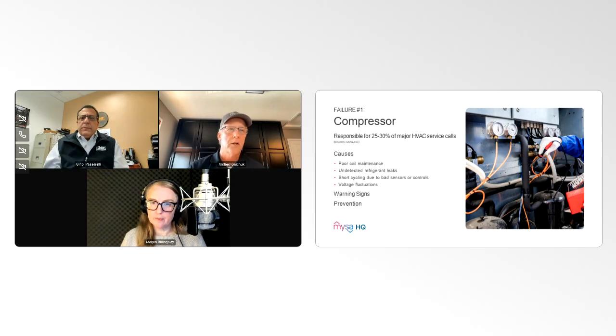The compressor itself may be running intermittently. So when we look at this runtime report here, if you look at, for example, the indoor line, where I can see the temperature decreasing and increasing and decreasing over the course of a day, that's typically an indication that a compressor itself may be overheating due to mechanical issues or electrical issues. And these thermal overloads are kicking in, turning off the compressor. From a runtime perspective, the thermostat is comparing temperature versus set point, and it's calling for that air conditioning. And so you can see in that graph, on the first few cycles, you're getting normal intermittent operation, maintaining a set point, but gradually things are getting worse to the point where the compressor is simply not running effectively or consistently, and therefore the thermostat is calling for constant cooling because it's just never meeting set point.